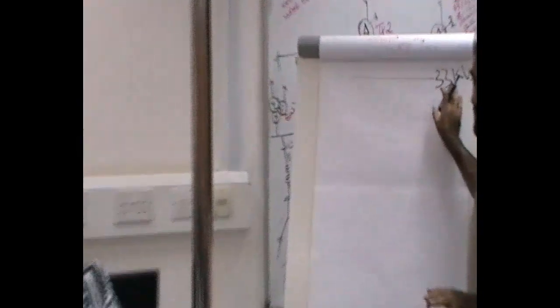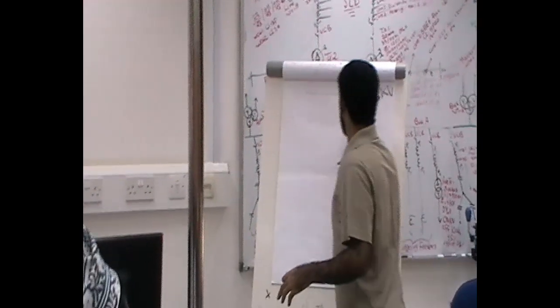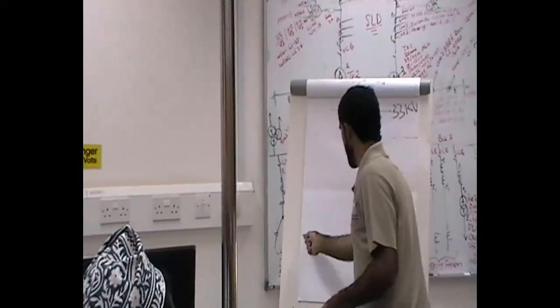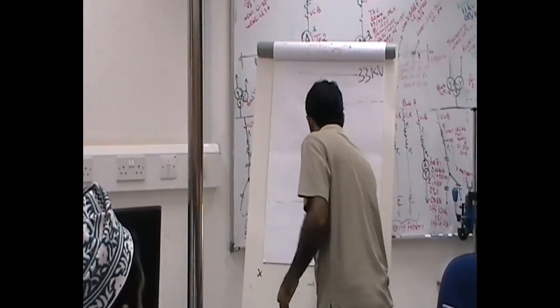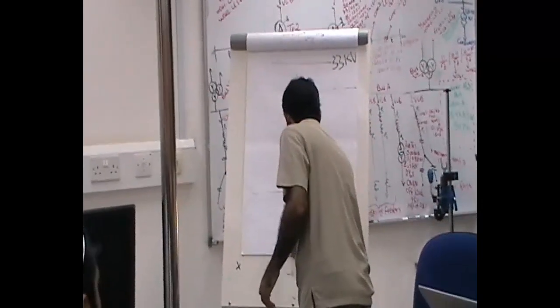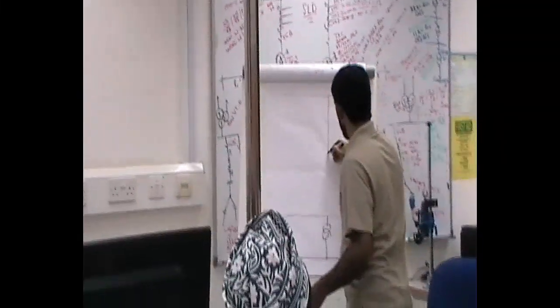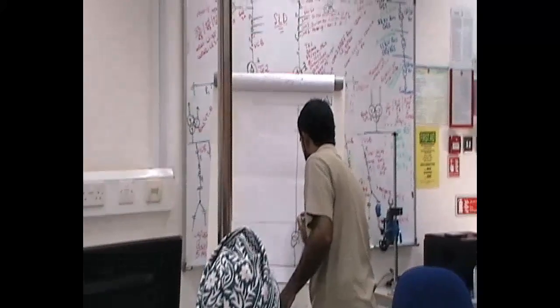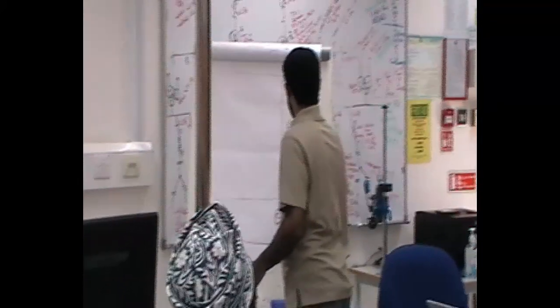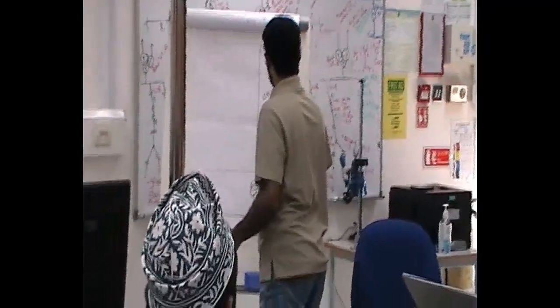Basically, if the line is a cable, differential is protecting only the line. So zone 1 is backup for differential. If you have a differential line, he will show it up there. I could explain it here. I have a 33 kV bus bar. Alright? This is a remote station by itself. And I have here another substation where I have a transformer and an 11 kV bus bar. This is 11 kV. If I have a line from here to this substation, here I have a circuit breaker, and here I have a circuit breaker. This line is about 10 kilometers of overhead line.